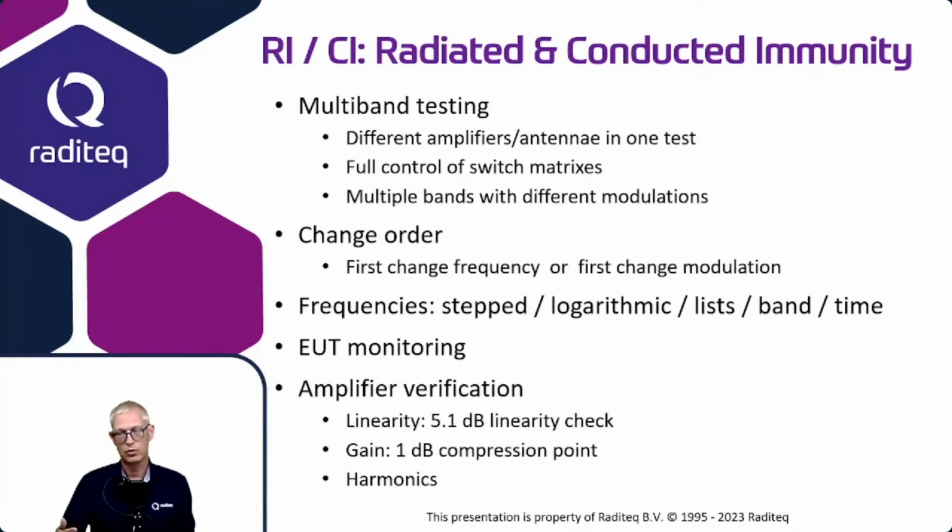And we also provide tools to determine and to measure the harmonics that are being generated by an amplifier. And this can be done on the power value, but it can also be done on the field harmonics that are being generated inside the chamber. So we also provide these tools that are needed for an accredited laboratory to verify that the amplifier is being correctly used.